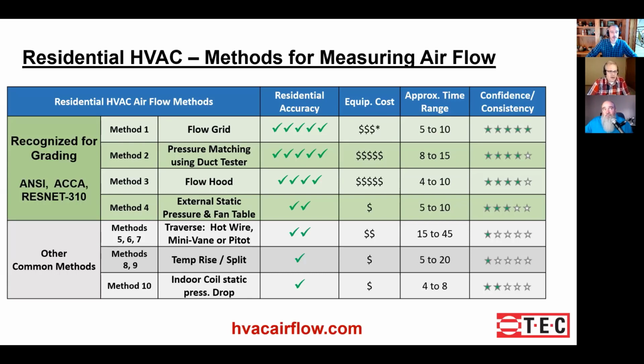These other methods have application, but as you go down these ones in the gray, it can get even harder. It takes more experience, and you have to really understand when this may or may not work. The temp rise, temp split, that one can work well, but you have to know where to get the probe.